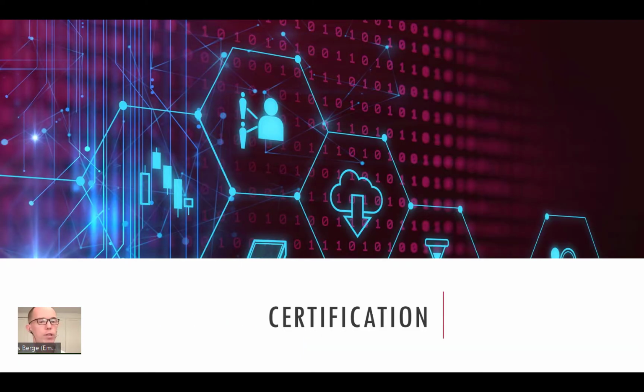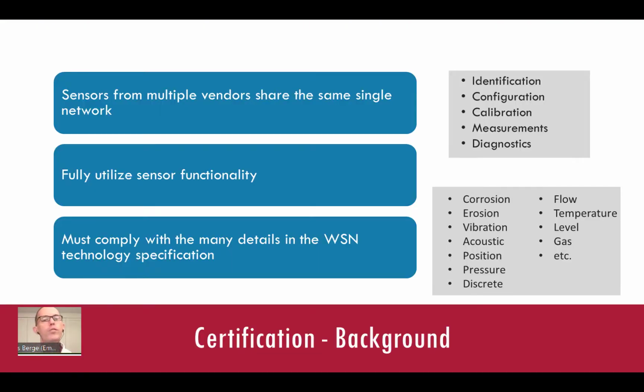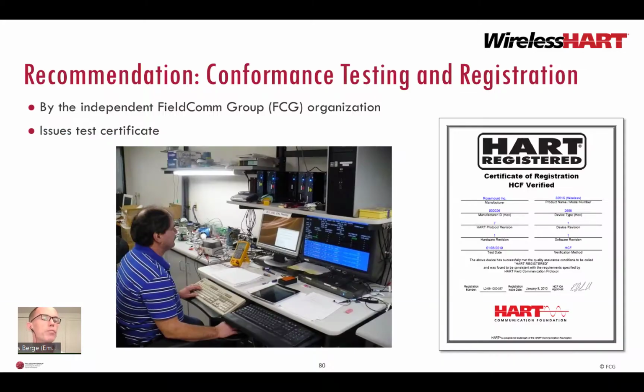Conformance testing. To solve all the use cases in a plant, you need wireless sensors from multiple vendors to be able to join the common wireless sensor network. It must be possible to identify, configure, and calibrate the sensor, and to get the measured variables and self-diagnostic status regardless of vendor. That is, the sensor must comply with the many details in the technology specification.